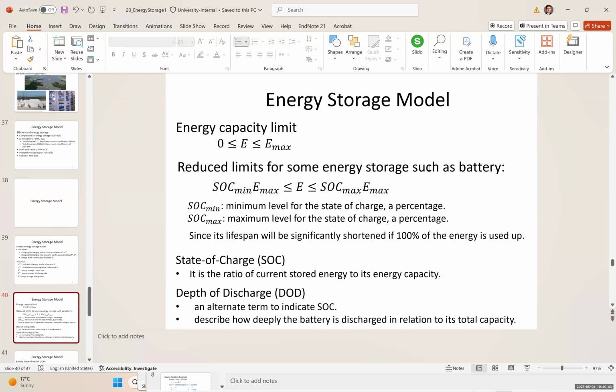There are reduced limits for some energy storage, such as batteries. We have the SOC minimum, which is a minimal level for the state of charge percentage, and SOC maximum, which is the maximum level for state of charge percent. Some batteries are going to be very unstable if you charge them over like 90-95%. So we want to keep the charge level usually between 20 and 80%, which is the optimal level. We don't want to reduce below 20% and increase over 80% because it's going to shorten the lifespan. Since the lifespan will be significantly shortened if 100% of energy is used up, again, we want to use it ideally between 20 and 80%. And most of the time it will be used only between 30 and 60% or 30 and 70%.